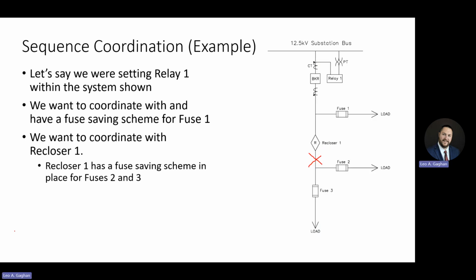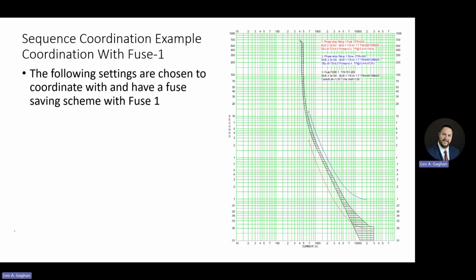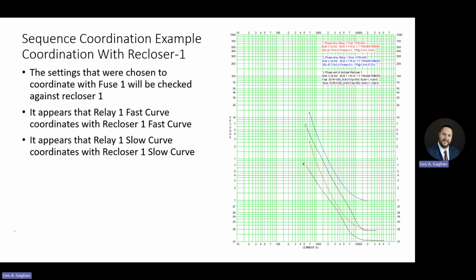As a recap, the sequence coordination is really intended to address the situation where we have two fuse saving schemes in parallel. We can see here, for example, relay 1, which trips the breaker, may want to have a fuse saving scheme with fuse 1, and then recloser 1 may want to have a fuse saving scheme with fuse 2 and fuse 3.